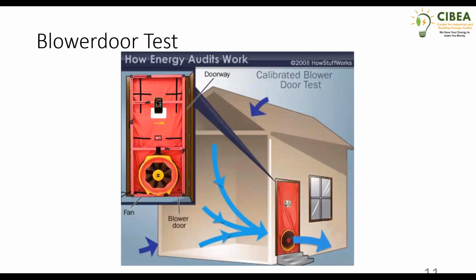You can see in this figure that once we install the blower door on the building, we open all the interior doors if it is a centrally ventilated and air conditioned building, and then usually we depressurize, or suck the air out of it, and keep it up to 50 pascals of negative pressure inside. Because of the negative pressure, all the nooks and corners where there are gaps, holes, openings, and cracks that can leak air in or out will start sucking air inside. And with the controlled flow of air, we can easily measure the air change level, or in other words, the leakage level or infiltration level of the whole building.